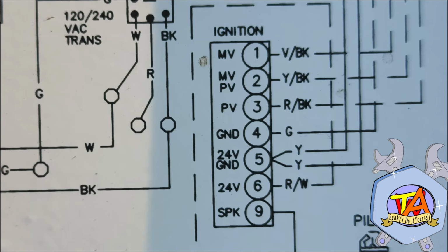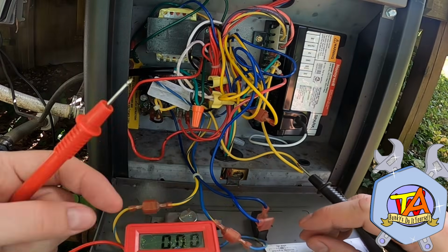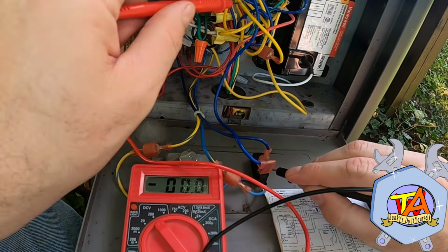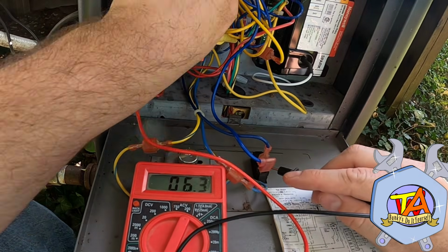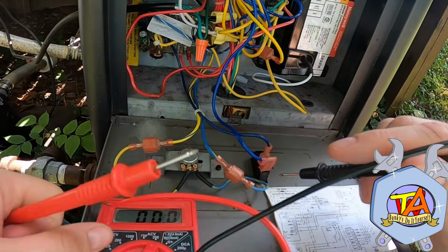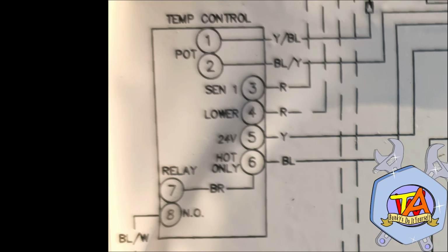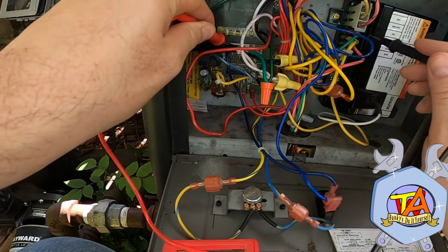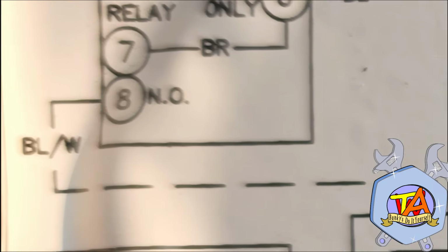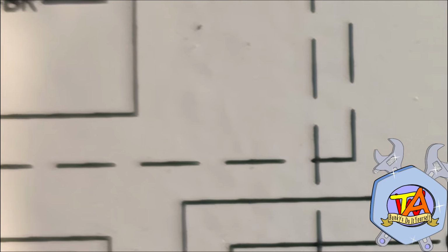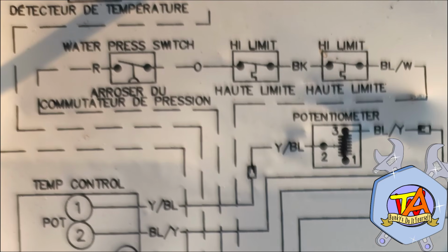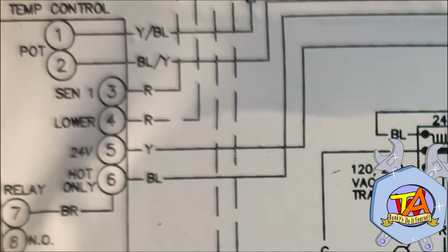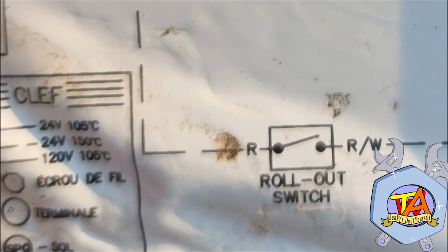I'm going to go through all of the connections on this board since I think it's an ignition problem. Since the only other board is a temperature control board, and since it gets its same 24 volt from a pigtail coming from the ignition board. And here's what I found. This blue and white wire had no power going to it, meaning it was one of these sensors that might be the problem. Any of these 4 sensors will stop the ignition process.